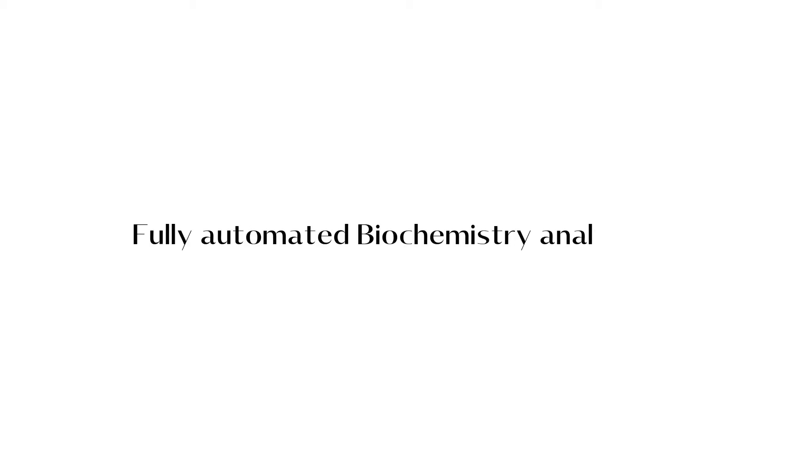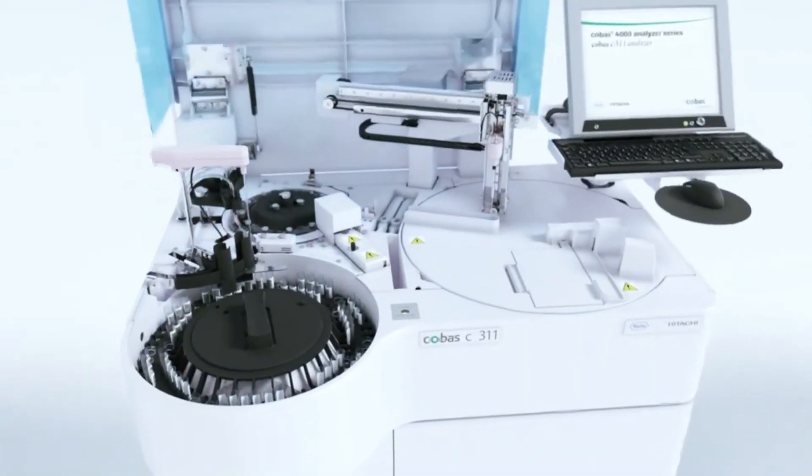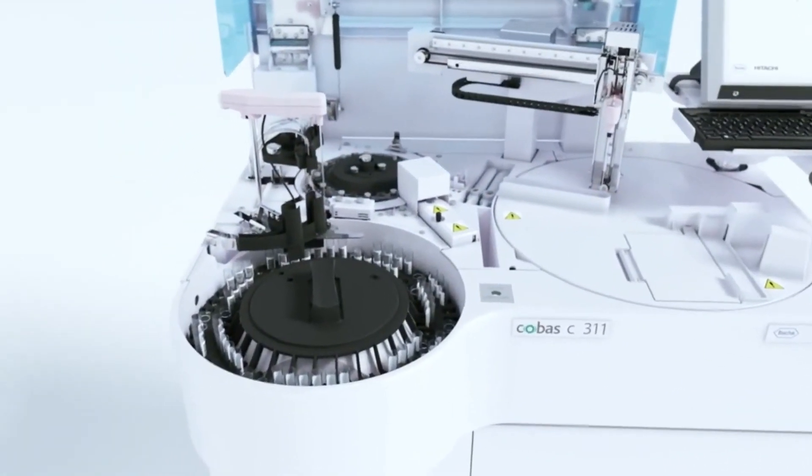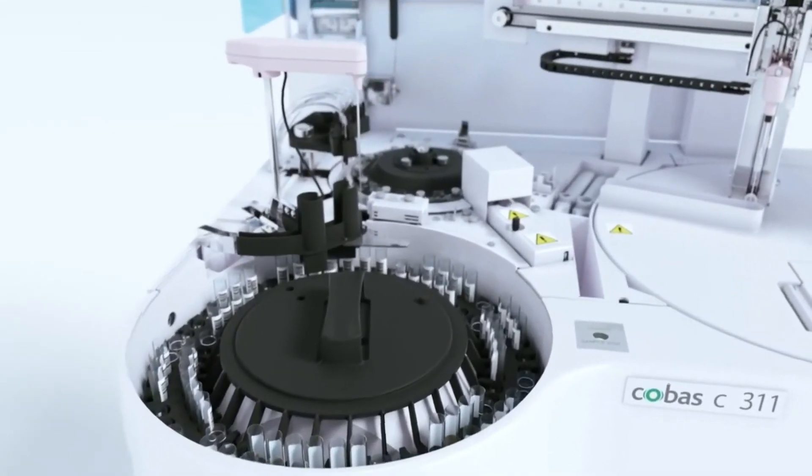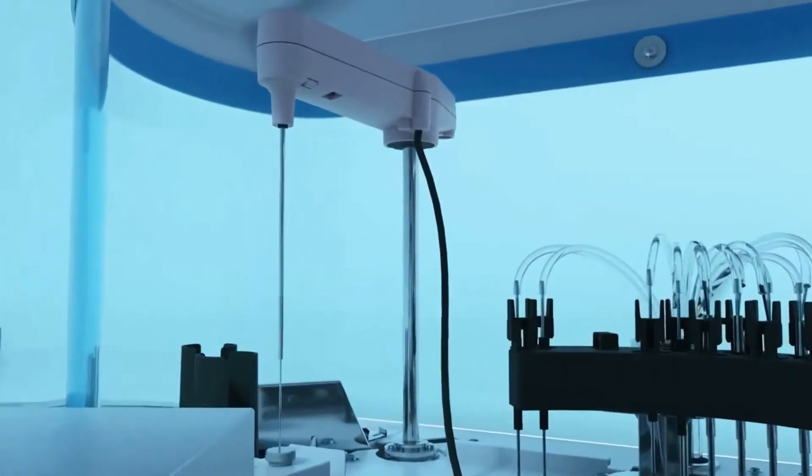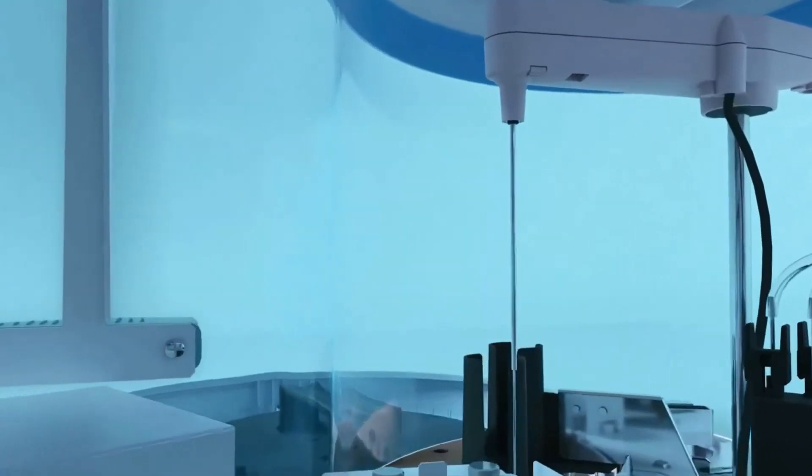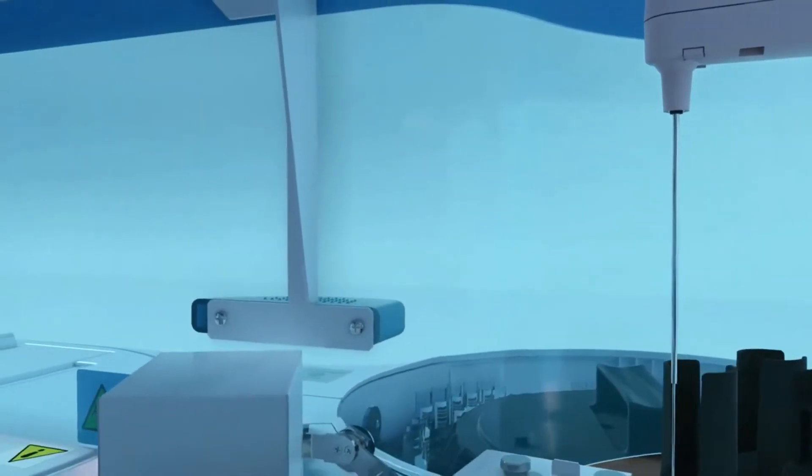The second type of biochemistry analyzer is the fully-automated biochemistry analyzer. Fully-automated biochemistry analyzers measure the concentration of certain proteins, enzymes, electrolytes, metabolites, or even drugs in the provided samples of urine, blood, serum, plasma, or other bodily fluids.